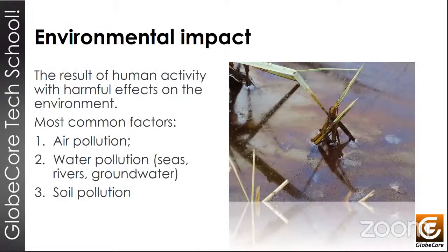Next slide, please. So the environmental impact of dumping the oil, if we change the oil, basically it's bad. Generally, as we are all aware, the environmental footprint of industries is quite significant, and the good thing is that it's becoming more important for companies to approach regeneration of oil more professionally. So mineral-based dielectric oil in our transformers is a hazardous pollutant, and it's also a human health hazard and remains so throughout the entire life cycle and even after that. So the greatest harm that the oil does, it does to aquatic ecosystems and to human health. And it can contaminate the environment in many ways.